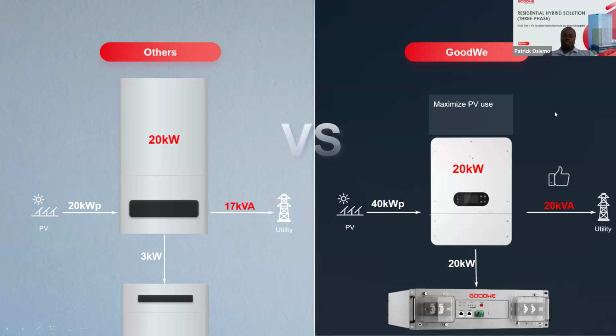Now look at the GoodWe ETLV series. This is a new feature, new brand, new specs, new technology. You can see for a 20 kilowatt hybrid system for a home, you can connect up to 40 kilowatt peak of PV. Now, how do you use this 40 kilowatt peak? The inverter itself can still output 20 kilowatt to support your loads, your AC, and then the remaining oversized PV, which is also 20 kilowatt, can be used to charge your batteries. So technically, you're actually buying a 40 kilowatt inverter, but still rated at 20 kilowatt. You have a 20 kilowatt output on the AC. At the same time, you have a 20 kilowatt output to the DC to charge your batteries.